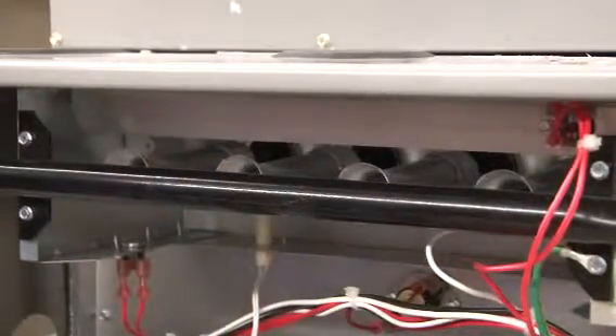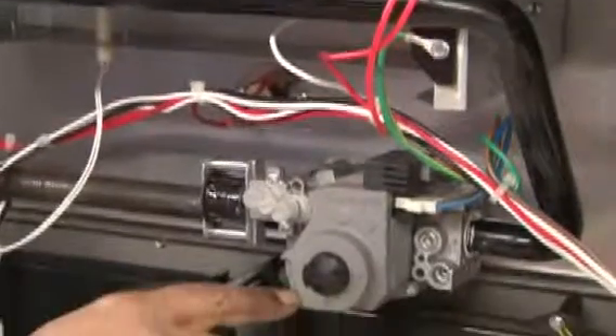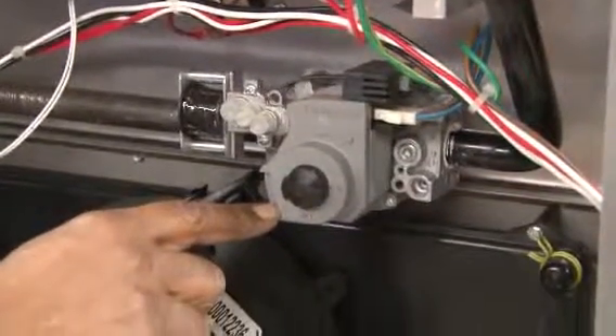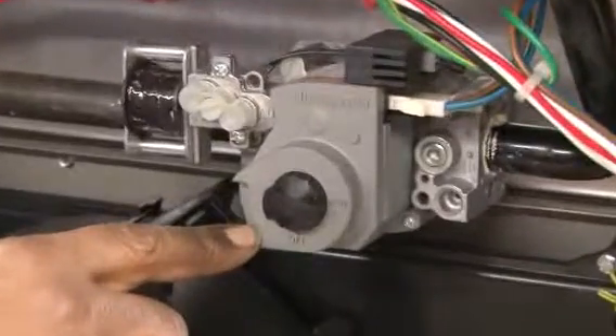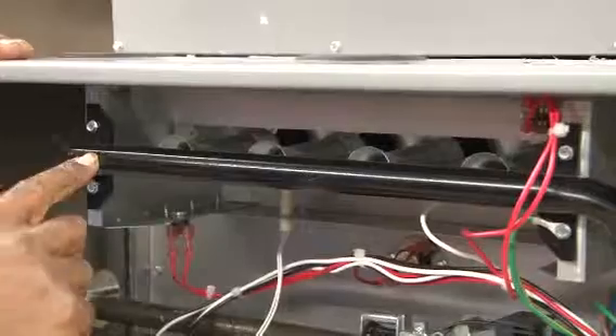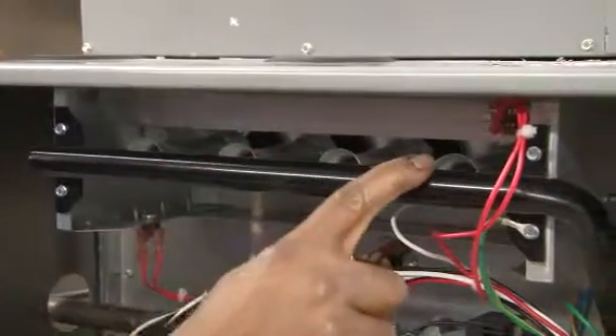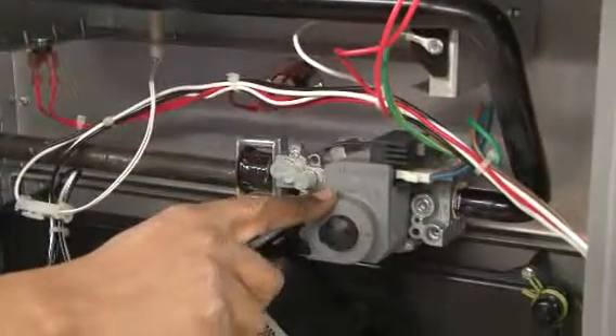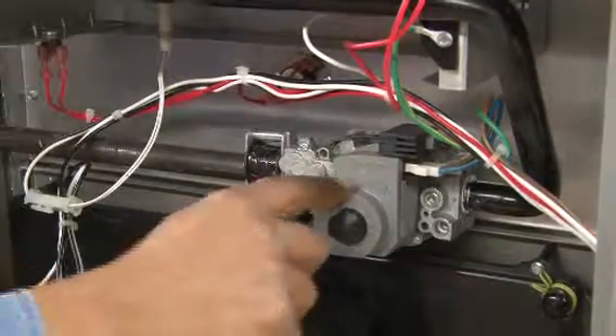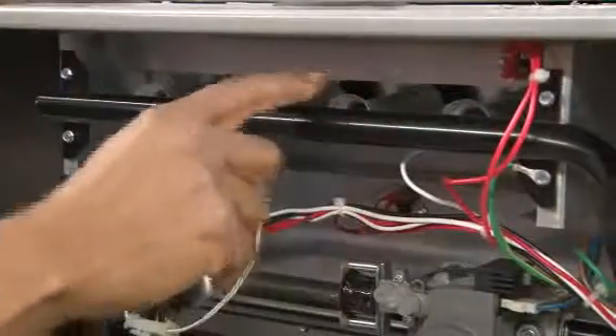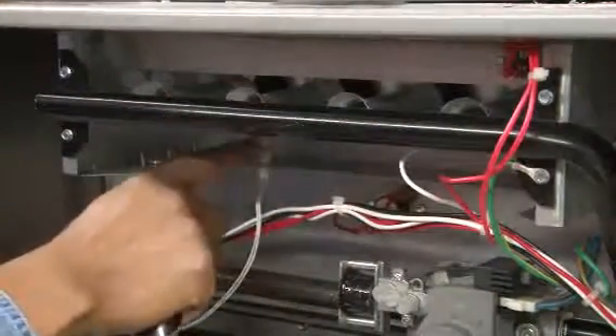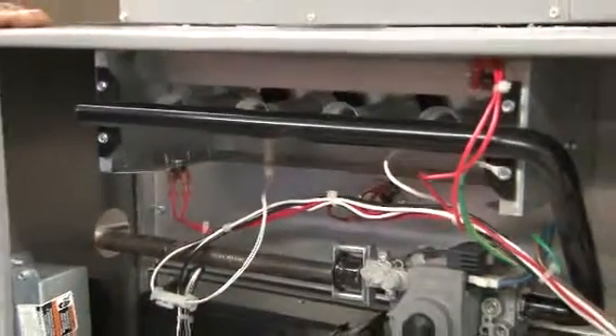This is the combination gas valve, and this gas valve is designed to stop the flow and to start the flow of gas into the burners here. So this bar here is actually a pipe, and this pipe is the manifold. And the manifold has orifices, one for each of the burners. So as this is energized by 24 volts, it will allow gas to flow through the pipe into the manifold and through the orifices into the burners, and the flame will go inside of the combustion chamber.